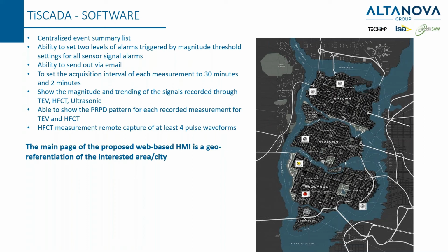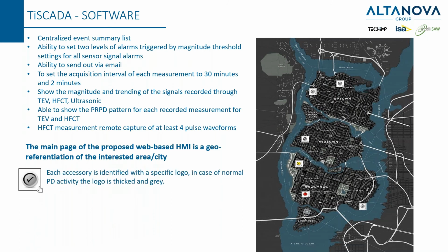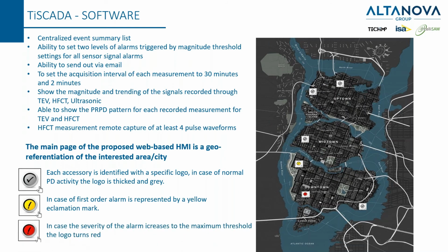So basically on the main page, we are used to provide this map of the city where there are substation as a first level, substation with the system installed. Each accessory is identified with a specific logo. In the case of a normal PD activity, the logo is thick and gray. In case of first order of alarm, is represented by the yellow. And of course, when it comes to critical, the color is marked as red.